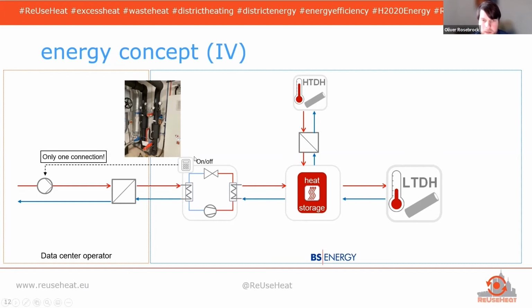So the heat pump can give a signal to a pump on the data center operator side to start the volume flow that goes over the heat exchanger. So there's a signal on or off, start operation. Please start the operation of waste heat recovery, and then everything is fine. And this is also linked to the heating demand. Additionally, for the additional cooling demand, the data center has an additional cooling machine installed.